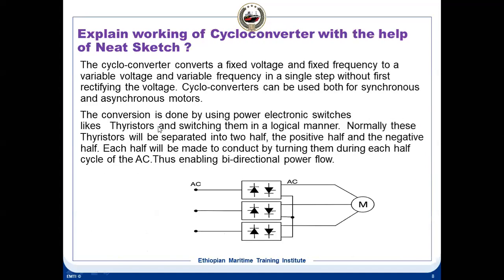Then a cycloconverter: explain the working of a cycloconverter. As I told you, we have 3 converters: the load commutated inverter, the cycloconverter, and the voltage source inverter, which is the same as a VFD. In a cycloconverter, we are using only thyristors without a DC bridge. There is no DC in between. The input is directly fixed AC, fixed voltage, fixed frequency, into variable voltage, variable frequency. The output frequency can be increased or decreased.